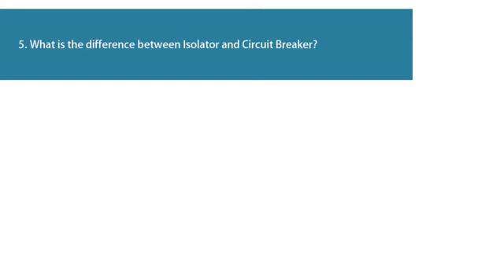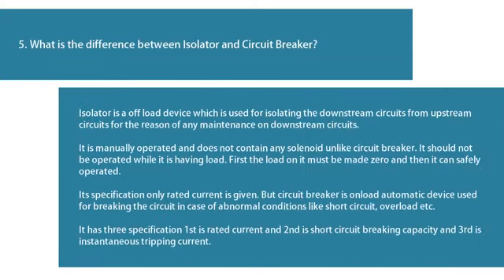Question 5: What is the difference between an isolator and a circuit breaker? An isolator is an off-load device used for isolating downstream circuits from upstream circuits for the purpose of maintenance. It is manually operated and does not contain any solenoid unlike a circuit breaker. It should not be operated while under load — the load must first be made zero, then it can be safely operated. Its specification only includes rated current. A circuit breaker, however, is an on-load automatic device used for breaking the circuit in abnormal conditions like short circuit or overload. It has three specifications: rated current, short circuit breaking capacity, and instantaneous tripping current.